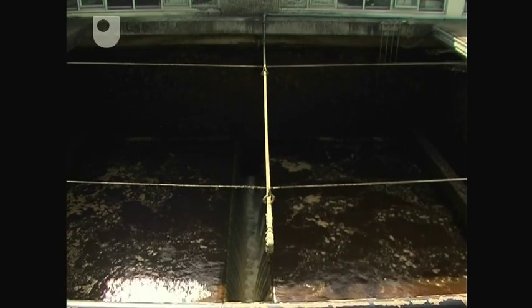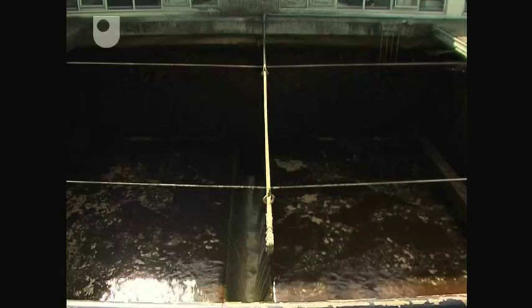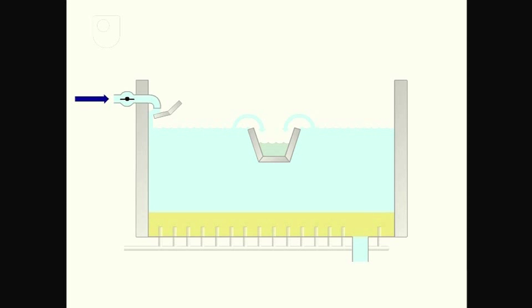The dirty water is sent to lagoons where the solids again settle out and once more the supernatant flows back to the reservoir. Once the outflow is seen to be clean, the backwashing cycle is terminated. The tank is filled and filtration begins again.